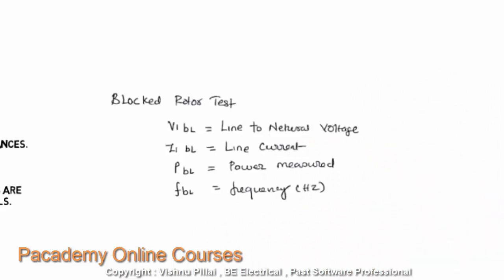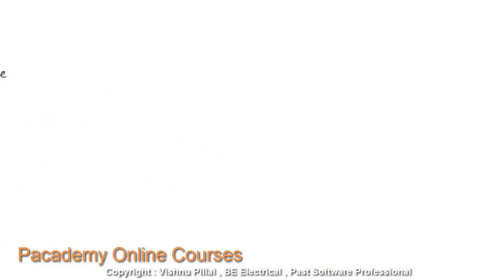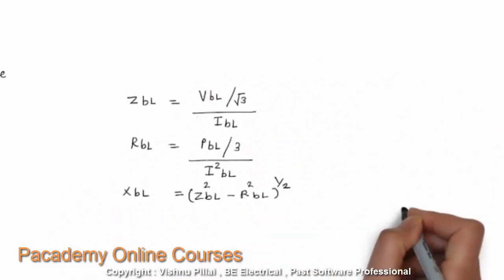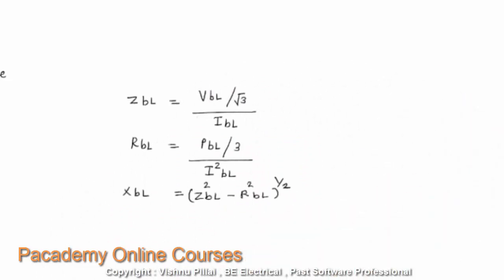In the blocked rotor test, the line-to-neutral voltage VBL is measured, I1 is the line current measured by the ammeter, power is measured using the two-wattmeter method, and the frequency is noted. The impedance during the blocked rotor test is computed as (VBL/√3) / IBL — essentially V divided by I.